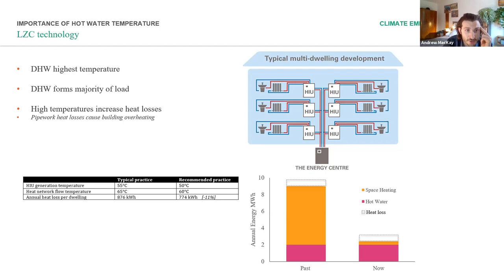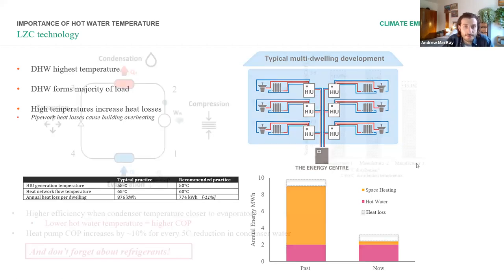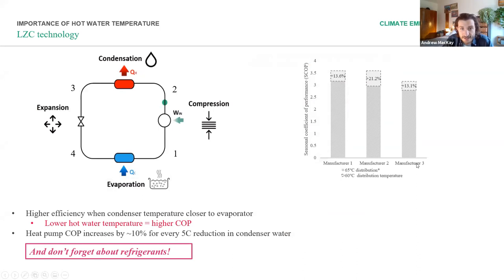So just by dropping the temperature from hot water in a flat at 55 degrees down to 50 degrees, it brings our network temperature down by 5 degrees as well, and gives us straight away an 11% reduction in heat losses through that network, which is a huge benefit. So you can move on one more slide, please. And it doesn't stop there.